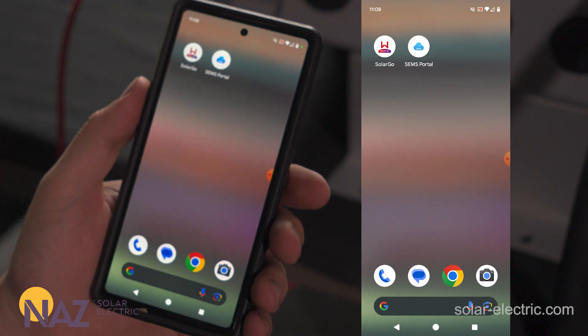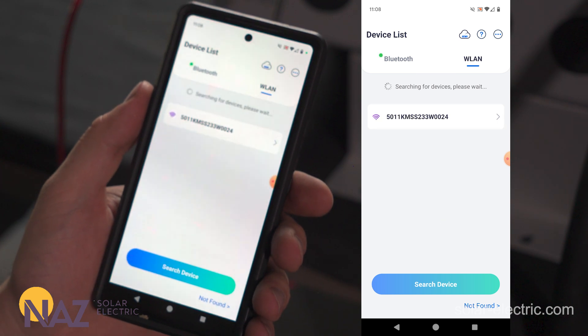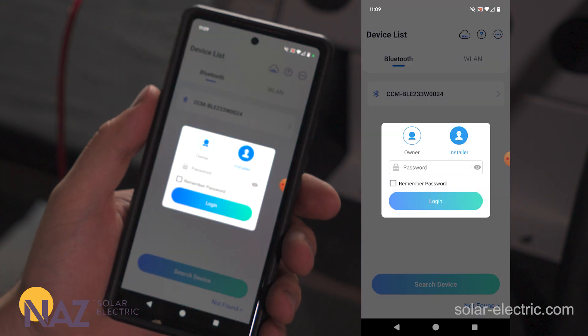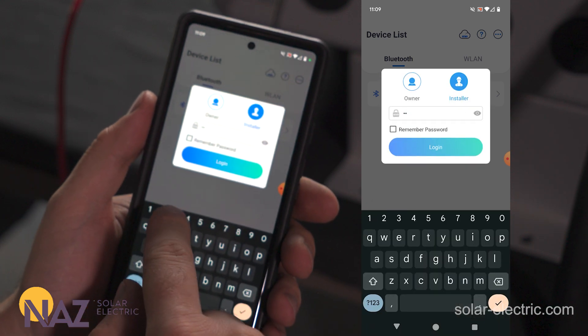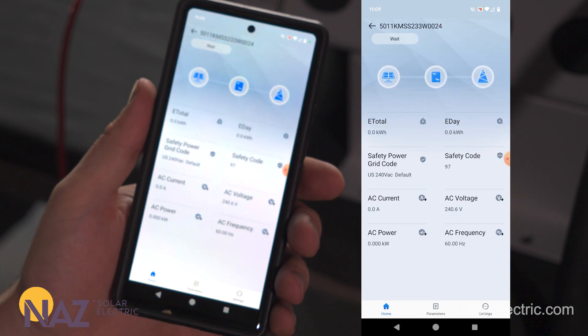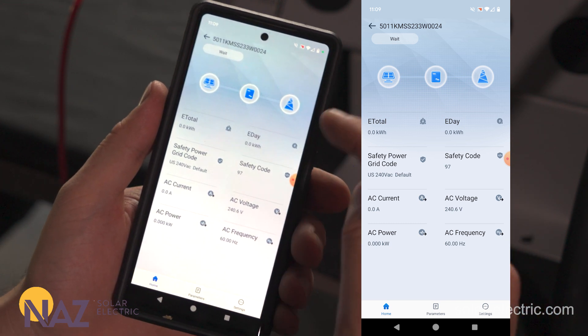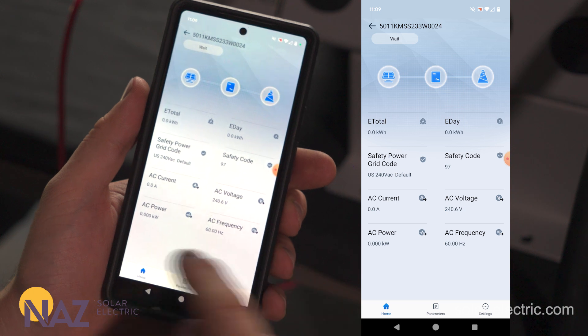Now that you have the apps downloaded, let's go into SolarGo and connect to the inverter so we can get Wi-Fi connected. This GoodWe US 30 uses Bluetooth, so we're going to go to Bluetooth, pull down and scan for devices. We've already found the device; we're going to click on it and use the default password to connect to the inverter, which is 1-2-3-4-5-6-7-8. We're going to log in and here at the overview screen we can see it's waiting for solar, plus an overview of energy production for the day and grid voltage.